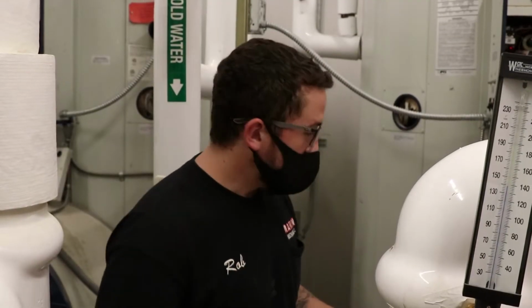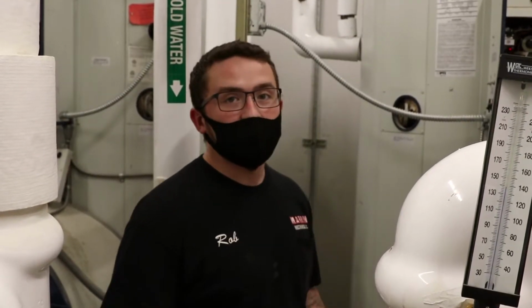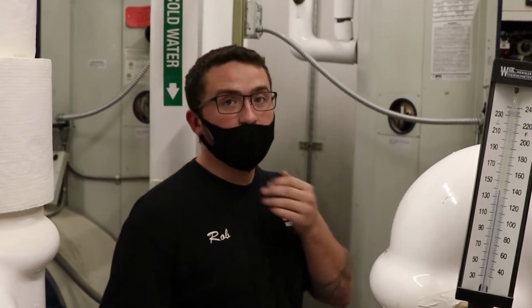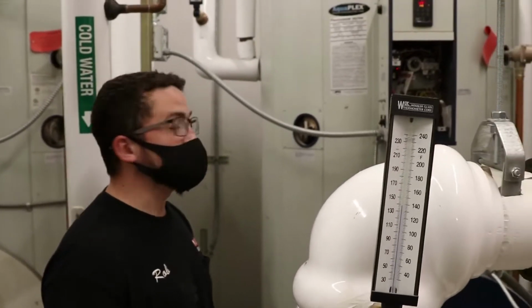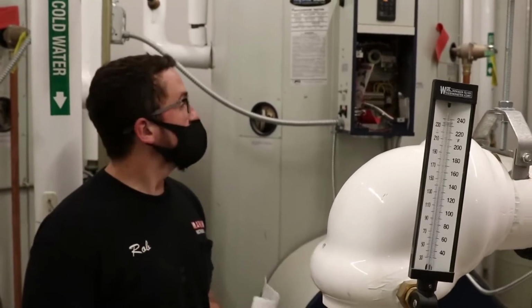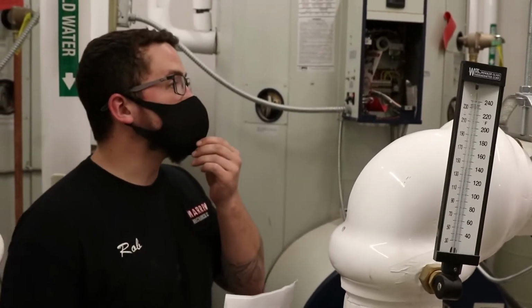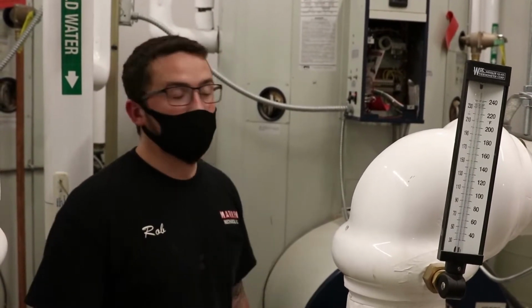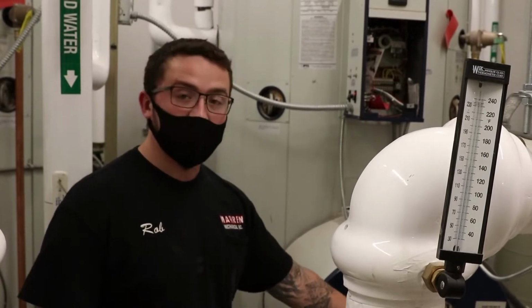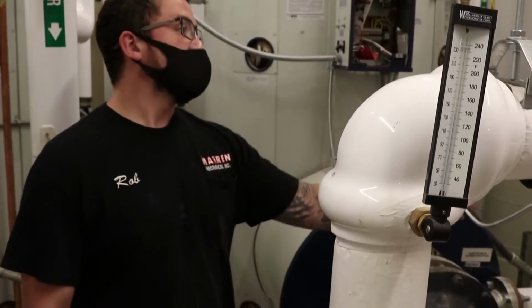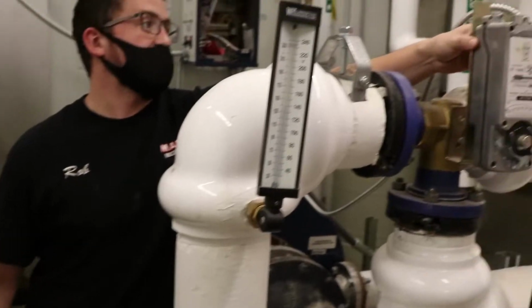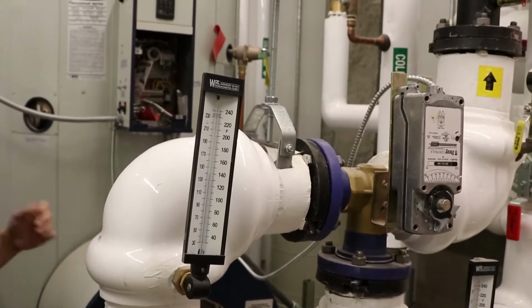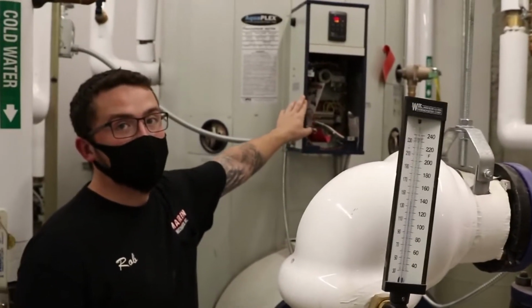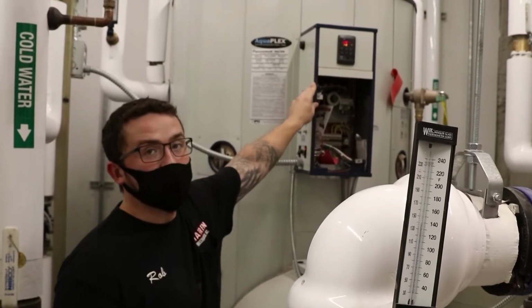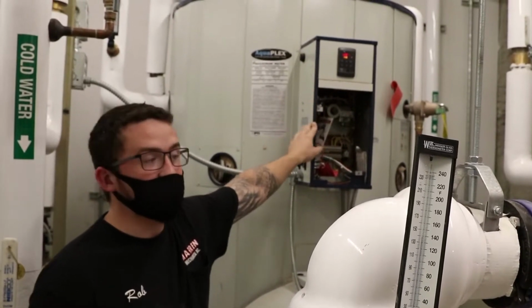All right, so today we're going to be going through training on these two PVI quick draw water units. First I'll talk about normal operation of them. They use boiler water to heat domestic water. This is done through this heat exchanger that you can see here and this boiler water control valve. So the units are currently set to 140 degrees. When they drop to 135 degrees, a call for heat is initiated.